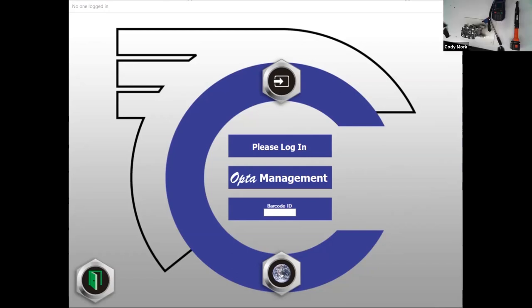Give it a few more seconds here for any other questions. Another question here, do I need a wrench loader to calibrate a click wrench using the click dip? No, you do not. You do not need a loader. You can do that manually, and that's how I was doing it here in my process. As you can see, I was pulling it by hand. So yes.